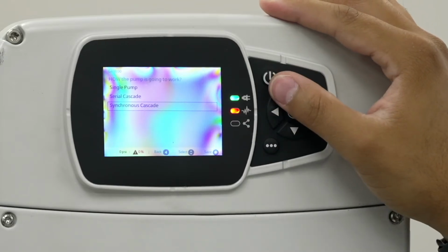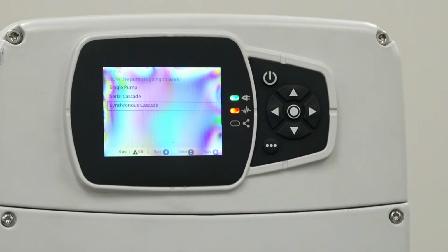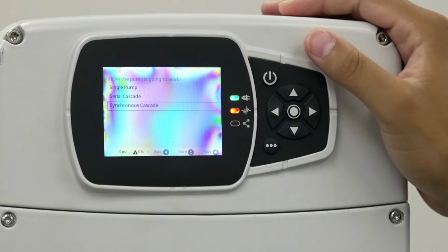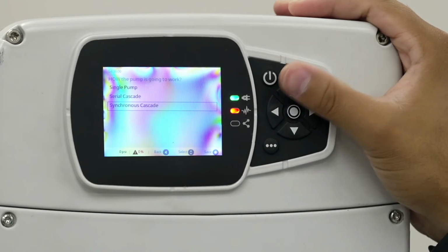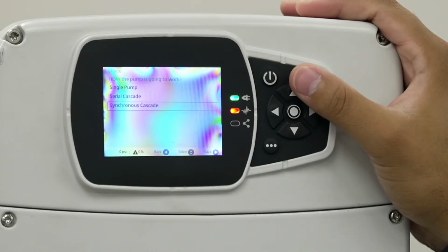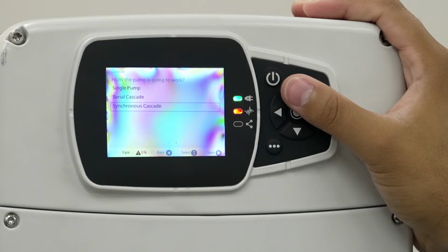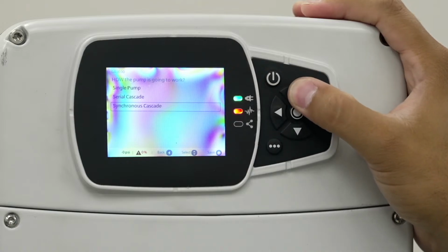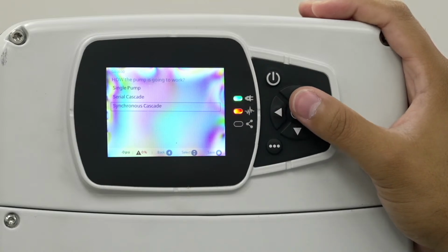Synchronous cascade is kind of what it sounds like. So all pumps in the system are going to run at the same exact speed to maintain the set point. They all will speed up and slow down at the same exact speed to maintain your set point. So the difference is that serial cascade is a little bit more accurate at hitting a pressure set point. It's not going to overshoot or undershoot, as one single VFD is ramping up and down. Synchronous cascade is a bit more efficient. Now you don't have multiple pumps running at full speed. They're all running at a reduced speed. You're going to have a much more efficient application. However, it's a little bit less accurate. You may see a little bit more overshooting or undershooting of your set point initially when it's ramping up or down. However, if it's not really a critical application, we would obviously recommend synchronous cascade just to get a little bit more efficiency out of your application.